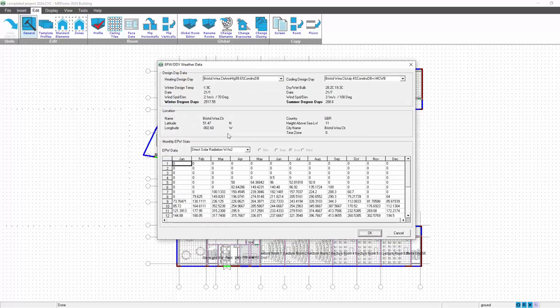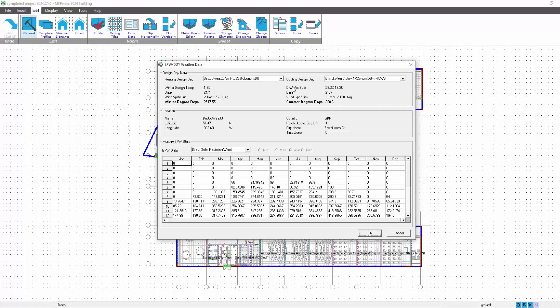Including the direct solar radiation, you have your cooling design day, your heating design day with your temperatures, wind speed. A lot of this is relevant to the calculations, by the way: winter design temperature, wet and dry bulb for your cooling loads. Then you have your direct solar radiation table. These are actually measured data, so we've moved away from the direct and diffuse basic factors that CIBSE uses, which is way out of date now. This affords a much higher level of accuracy.